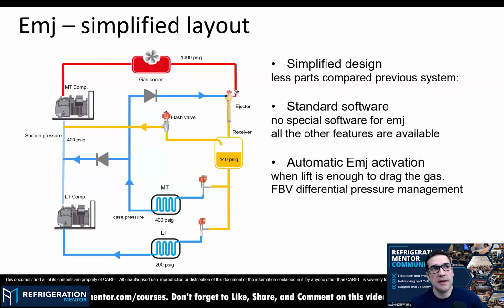Yeah, no, and that makes sense. The biggest thing is that if you're working on booster systems today and you have an electronic valve as your high pressure valve, this here is just another high pressure valve. It looks a little bit different than maybe what you're normally looking at, but it's the same. It's a valve that's opening and closing by an electrical signal from a couple of different sensors, pressure sensors and temperature sensors, to say we need to open up a bit more, we need to close off a little bit more. That goes back to a controller.